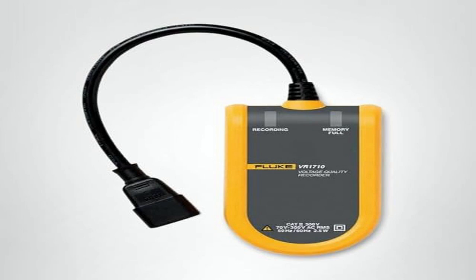Who should walk away from this product? If you're a hobbyist who only needs to verify that a single outlet isn't dropping below 110V, the VR1710 is overkill. The price point, the calibration pedigree, and the software learning curve all assume a professional use case. Likewise, if you run a large industrial plant that needs multi-phase, high-current monitoring across dozens of panels, you'll quickly outgrow the single-channel architecture of the VR1710 and look for a modular system with networked data loggers. In those situations, the money is better spent on a scalable solution rather than a single-unit recorder.